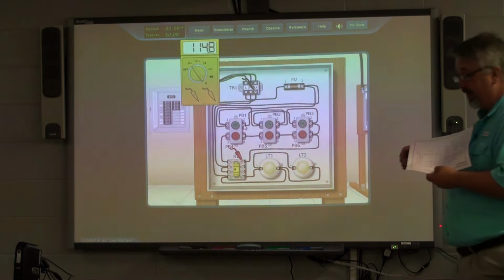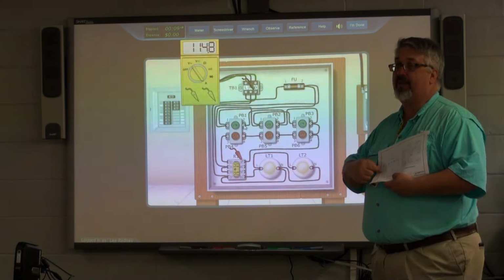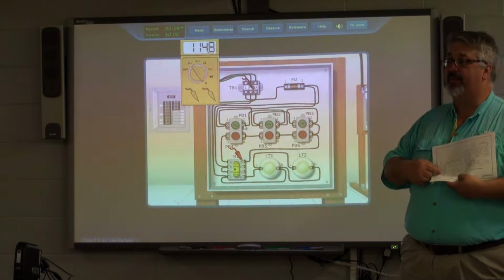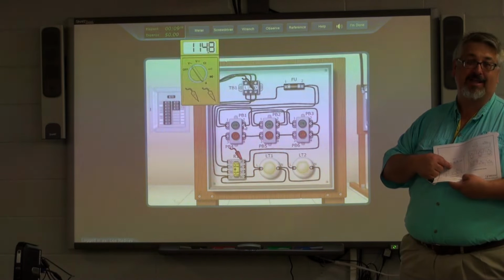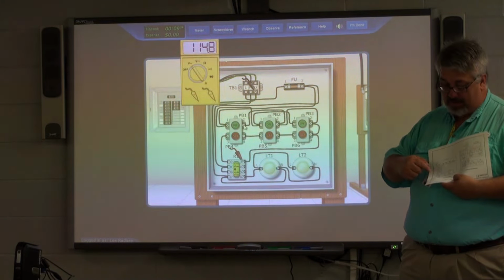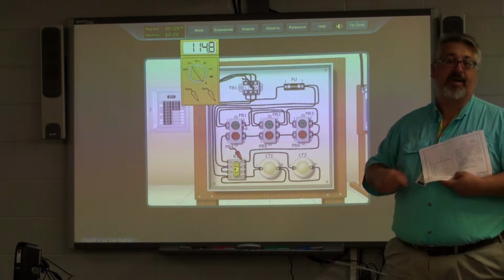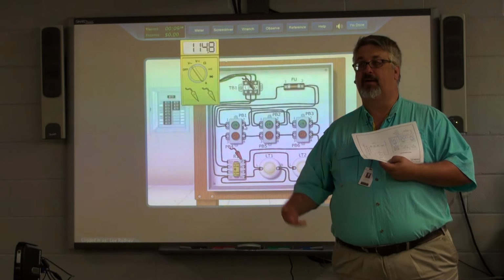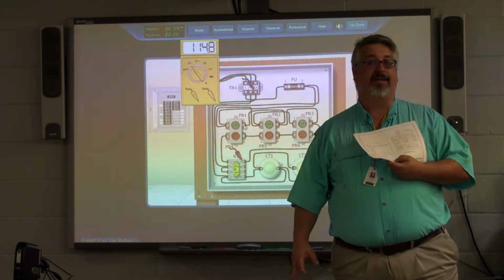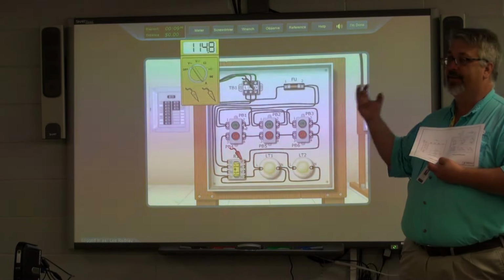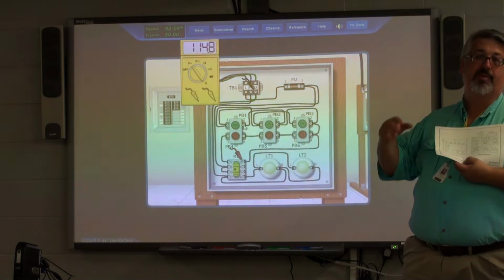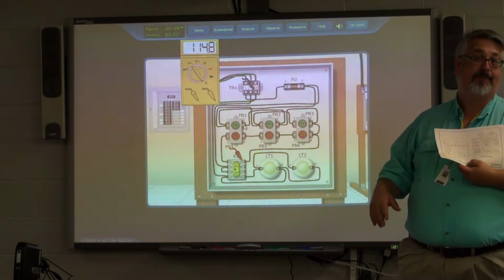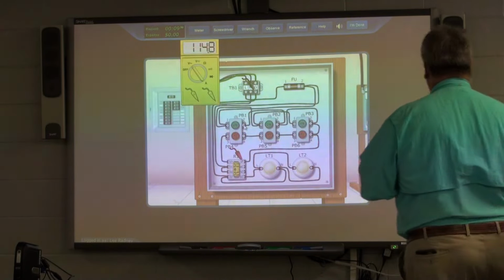As soon as we press that button, the 115 volts sitting on pin 1 goes over to pin 3. Whereas before we had to press any of these 3 buttons to make those lights come on and energize that coil, now pin 1 and 3 are bypassing or jumpering those contacts. That's what's latching this circuit in the on position.